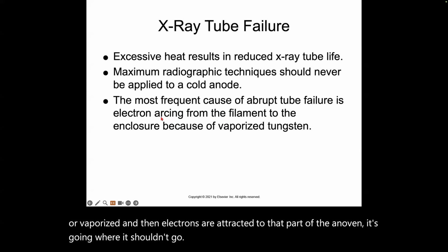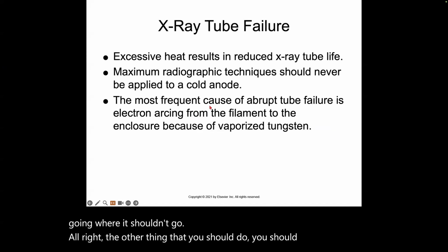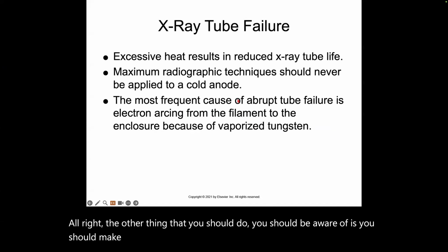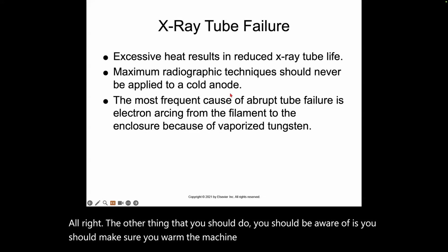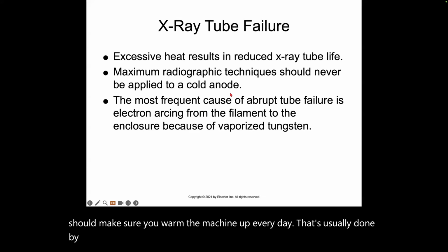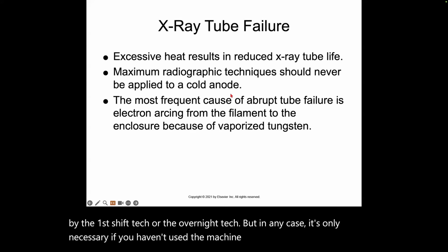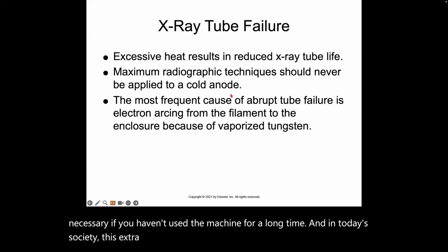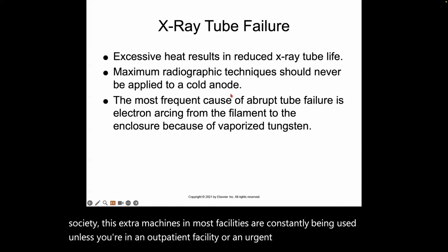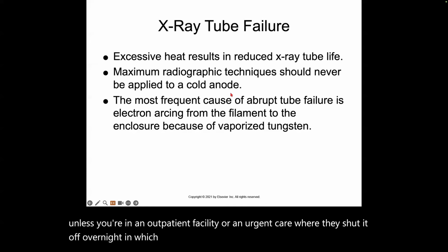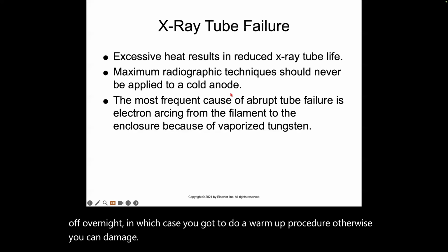The other thing you should be aware of is that you should warm the machine up every day. That's usually done by the first shift tech or the overnight tech. But it's only necessary if you haven't used the machine for a long time. In today's society, X-ray machines in most facilities are constantly being used, unless you're in an outpatient facility or an urgent care where they shut it off overnight. In which case, you have to do a warm-up procedure. Otherwise, you can damage the tube by using high exposures on a cold tube.